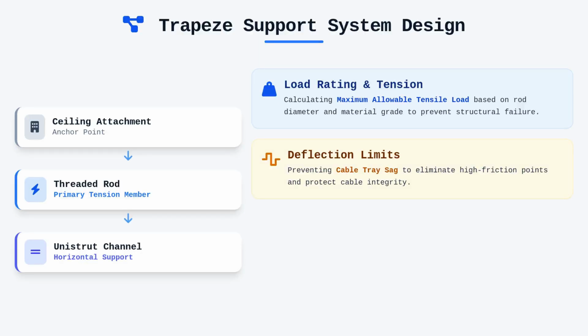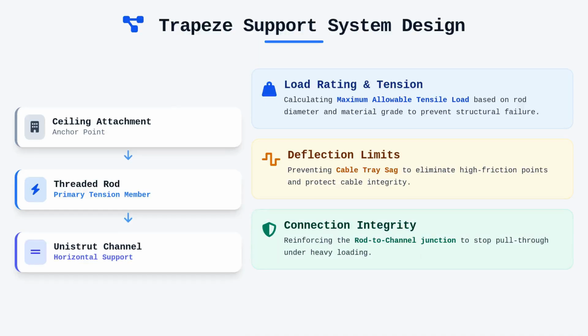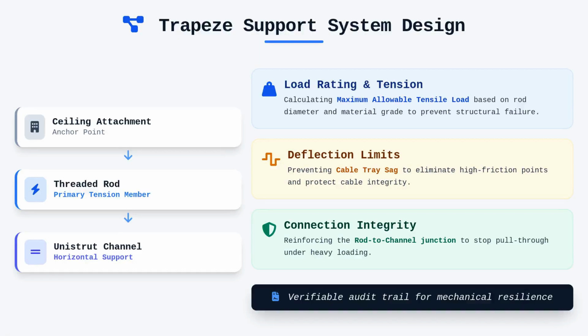If we have a long span of tray supported by a trapeze, we must verify that the horizontal channel, or unistrut, can span the distance without exceeding its allowable deflection limit. Excessive deflection is not just an aesthetic issue. It can cause the tray to sag, creating points of high friction where cables could be damaged during installation. Furthermore, the connection between the threaded rod and the trapeze channel must be reinforced to prevent the rod from pulling through the channel slot under heavy loads.